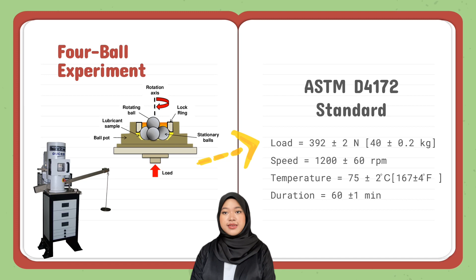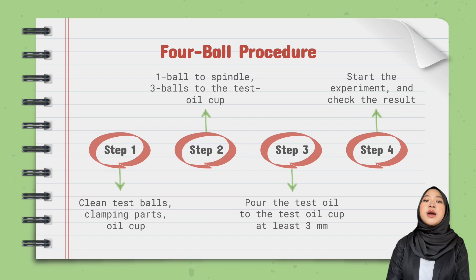So this is the summary of the 4-ball procedure. Start with cleaning the material and apparatus using the N-heptane, and then tighten 1 clean ball to the machine spindle and assemble 3 in the test oil cup. Then hand tighten using the wrench approximately 2.8 to 5.6 Nm. Next, put the oil sample into the test oil cup to a level at least 3 mm above the top of the ball. Lastly, run the experiment according to the parameters explained before and measure the wear scar on the 3 lower balls using the Aqilah microscope.